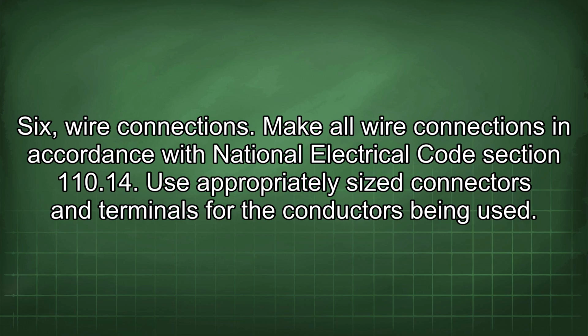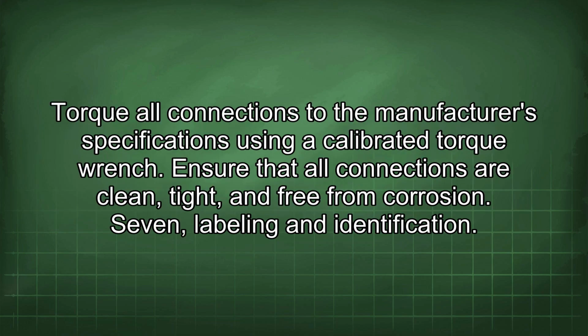6. Wire connections. Make all wire connections in accordance with National Electrical Code Section 110.14. Use appropriately sized connectors and terminals for the conductors being used. Torque all connections to the manufacturer's specifications using a calibrated torque wrench. Ensure that all connections are clean, tight, and free from corrosion.